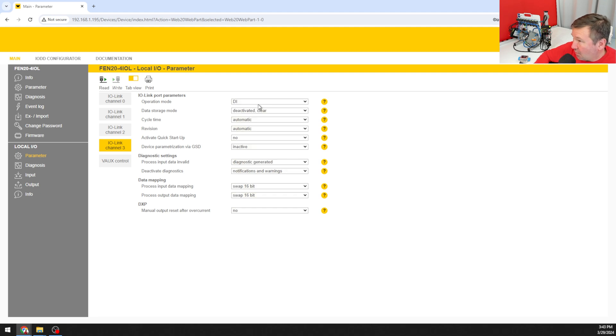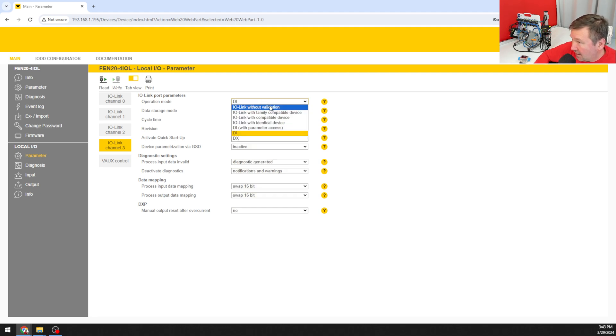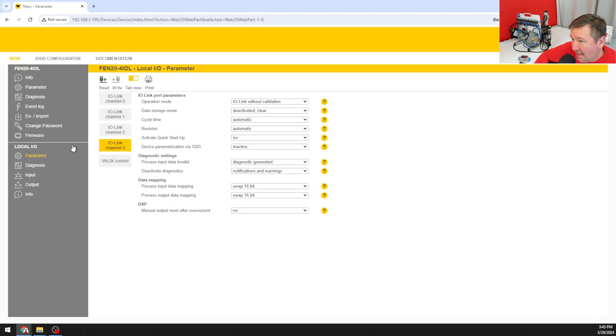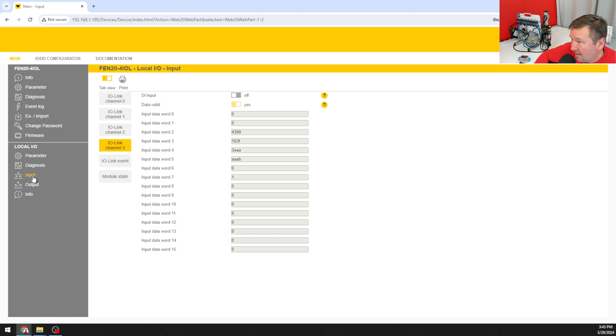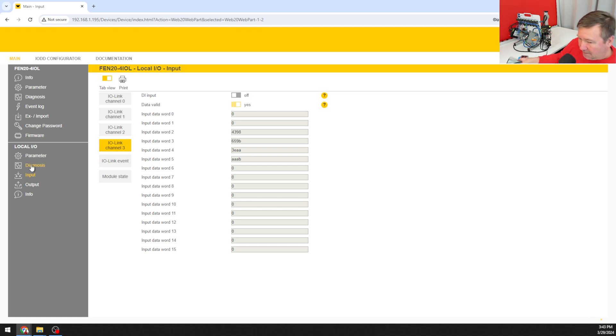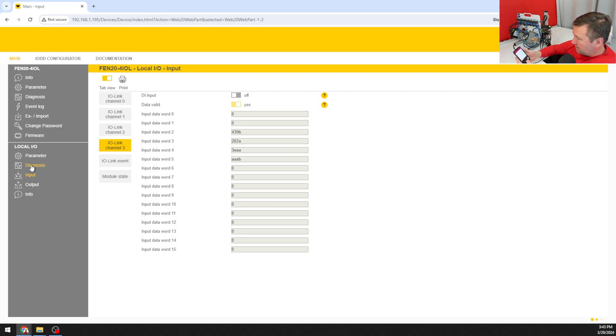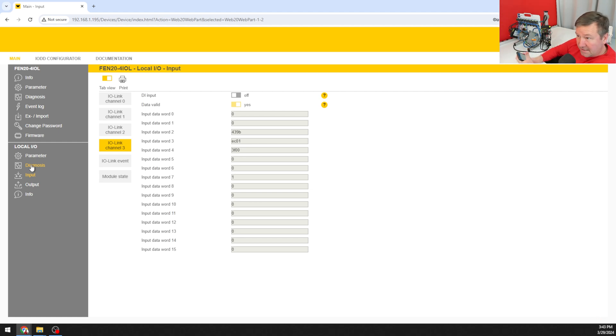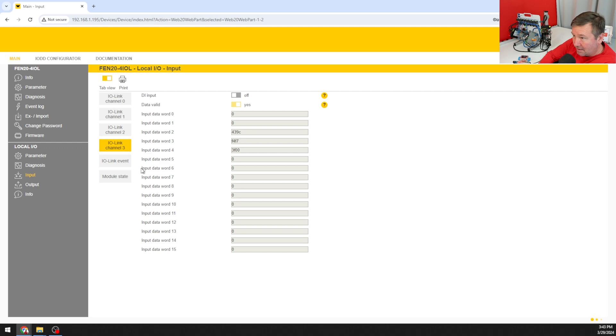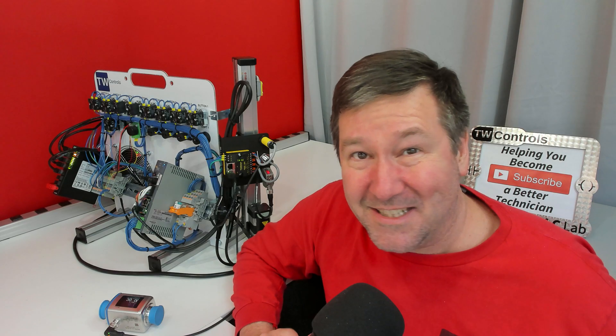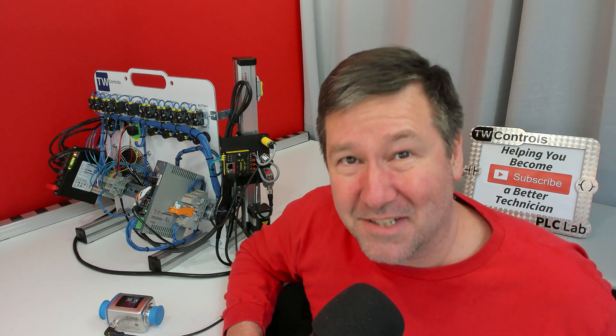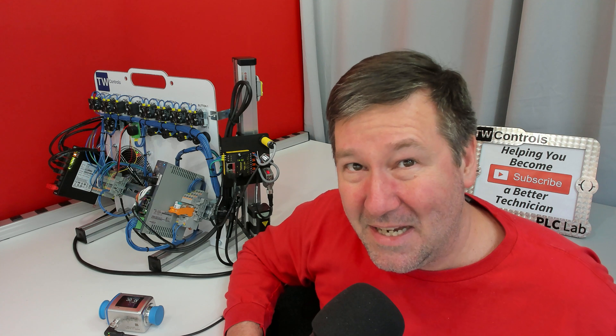Now I have a drop down for my operation mode and I'm going to select IO link without validation and click write. Now if I go to my input data I see I have some values going on here. If I go to the smart blue app and change my flow to 30 liters per minute, then we see quite a bit of numbers changing here in our input data word. The issue is I don't know what any of those numbers actually mean.